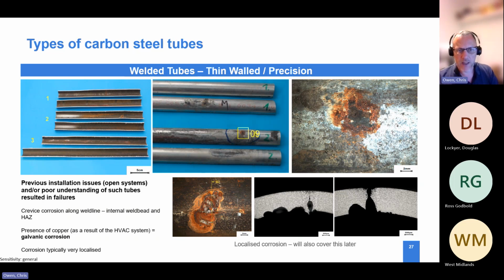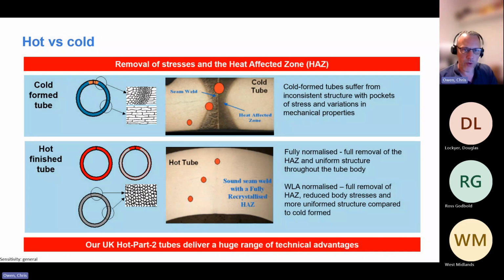The problem we have here is pipework which has been installed incorrectly, not maintained correctly, and not understood in terms of how application conditions can impact it. What we saw was pinhole corrosion as a result of galvanic corrosion reactions, causing thinning of the wall in a localized area. Because this is thin wall material anyway, it corroded and burst quite quickly compared to traditional tubes. This was all down to very localized corrosion as a result of issues which could have easily been mitigated.